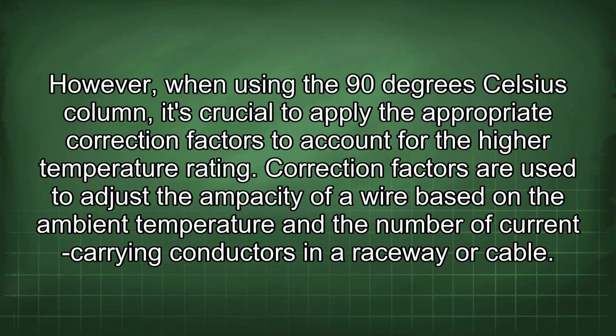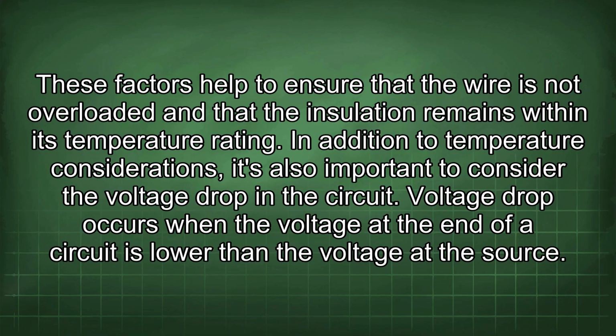However, when using the 90 degrees Celsius column, it's crucial to apply the appropriate correction factors to account for the high temperature rating. Correction factors are used to adjust the ampacity of a wire based on the ambient temperature and the number of current-carrying conductors in a raceway or cable. These factors help to ensure that the wire is not overloaded and that the insulation remains within its temperature rating.